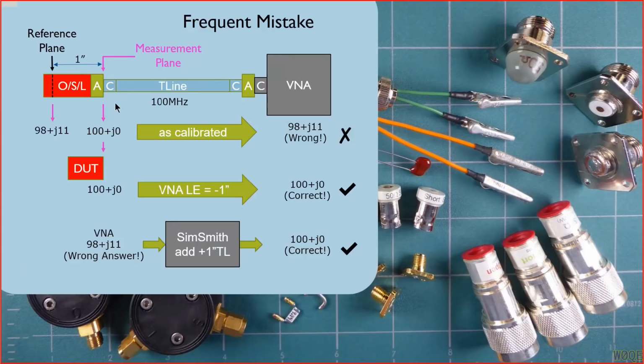So here I've taken the original drawing I had and expanded upon it somewhat. I'm assuming the problem is as follows. I have a device that I want to make a measurement on. The device is specified to have an input impedance right here of 100 plus J0 at 100 megahertz. It's got a connector type on it that mates directly with this connector right here. So once I remove my calibration stuff, I can just put the device under test right here and make a measurement. However, my open short load does not have the same connector type as the device under test, so I needed an adapter here to go from this connector type to the connector type here.